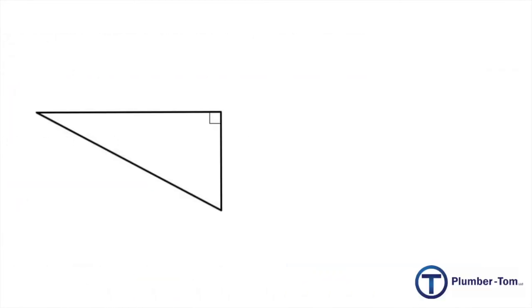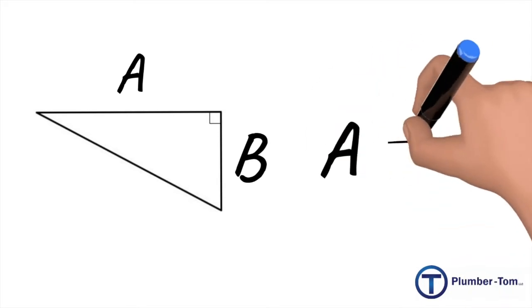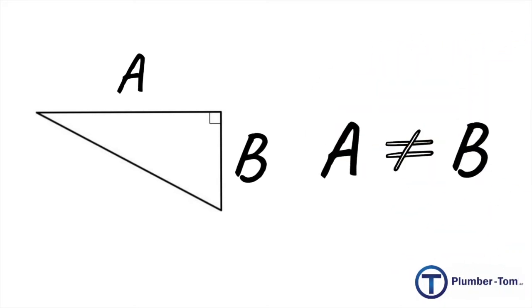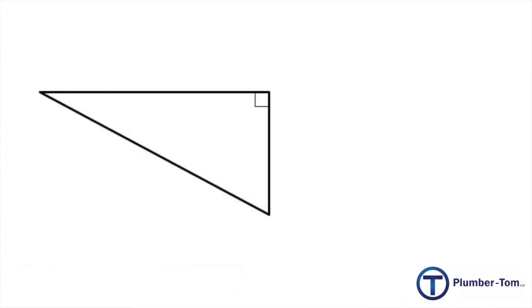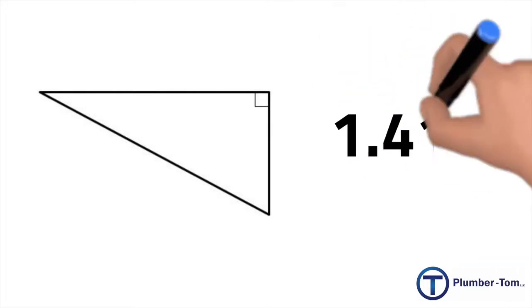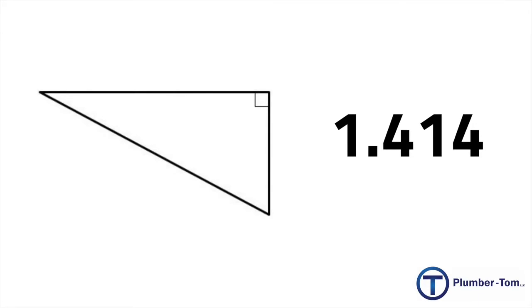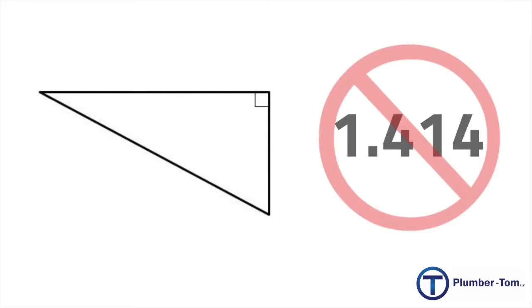In most cases, the triangle created by the offset and the rise has sides that are not the same length, so a does not equal b. In addition to the 90-degree angle, there are two other angles in this triangle which are not 45 degrees, and while they could be calculated, that's not something we need to know in order to calculate a rolling offset. It is important to note that because this triangle has two sides that are not the same length and we're not dealing with 45-degree angles, we cannot use 1.414 to calculate the diagonal.